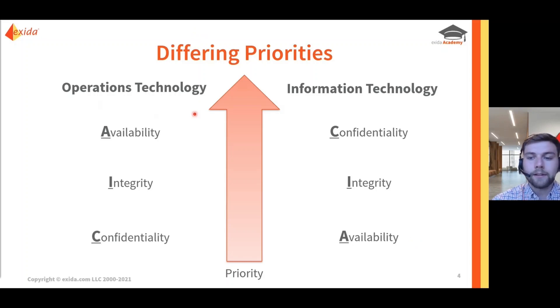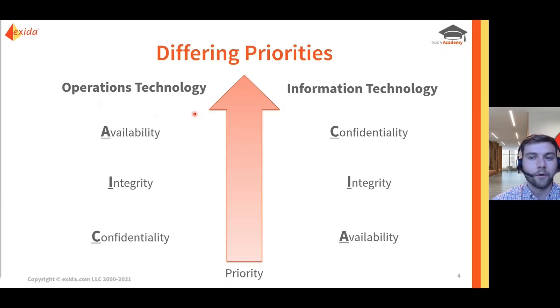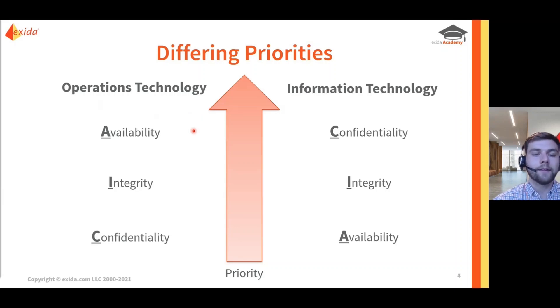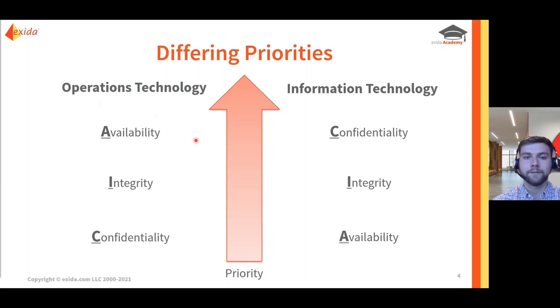On the other hand, when we talk about operations technology, availability is paramount and is the number one priority that must be maintained. For example, if the programmable logic controller is unavailable for five minutes, that could have a major impact on the system and would most likely result in a process shutdown or another undesirable event. The priorities on the OT side are actually the opposite of what we look at on the traditional IT security side.